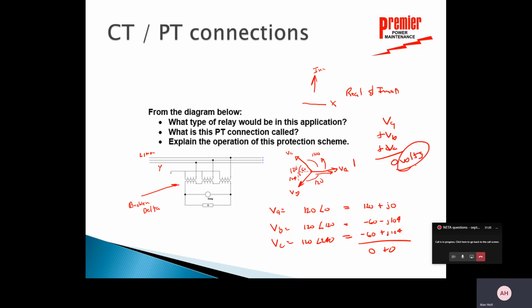So this broken delta configuration is looking at a situation where everything is balanced. If voltage A plus B plus C are all added together in the balanced situation, I have 0 volts there. But in an unbalanced situation, let's say I've got a ground fault and one of these voltages goes to 0, then all of a sudden it doesn't add up to 0. So for an unbalanced situation or a phase fault, one of these will go to 0, and all of a sudden I will have a voltage applied here.